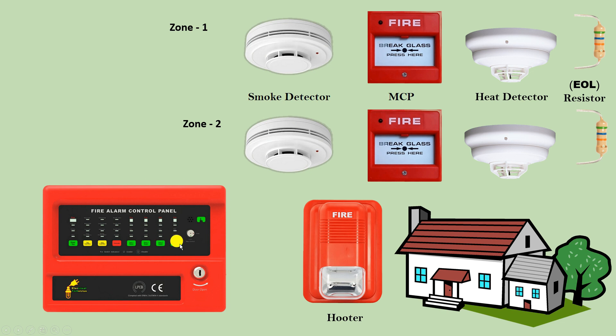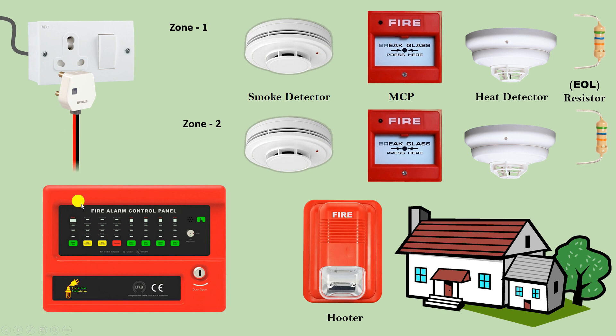To provide power supply to the fire alarm control panel we will use a switchboard, which already has a power supply connected. With this switchboard we use a plug top, and through this plug top wires will be connected to the panel. In some panels there is already a plug top; just connect it. If not, inside you will find terminals labeled phase and neutral — connect phase supply to phase and neutral supply to neutral.